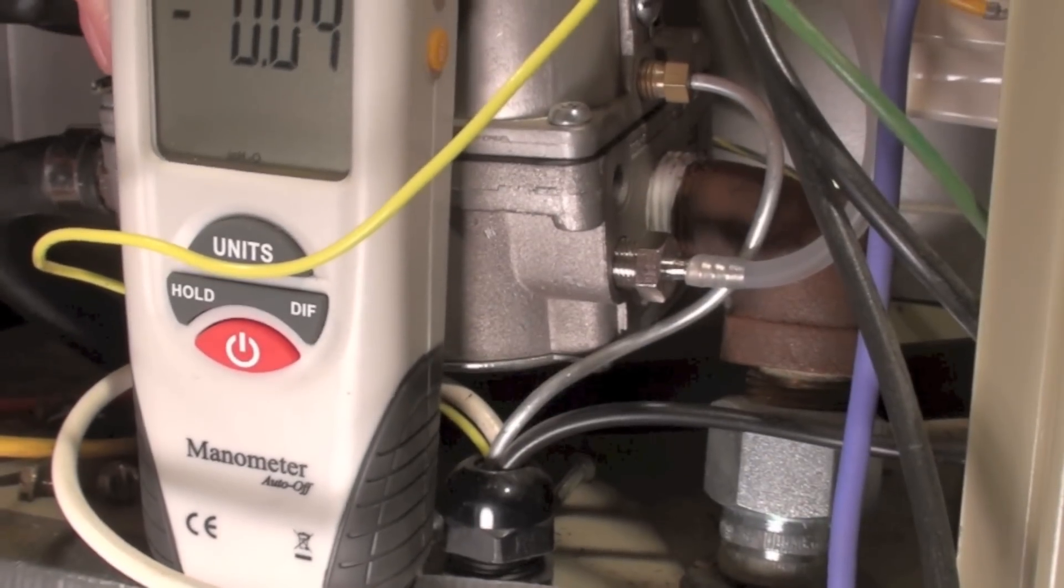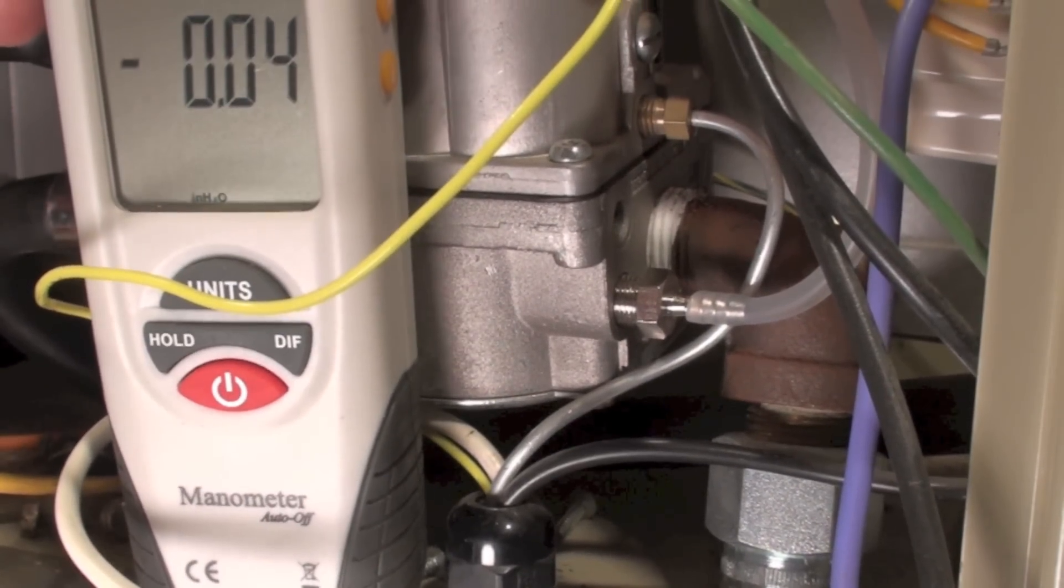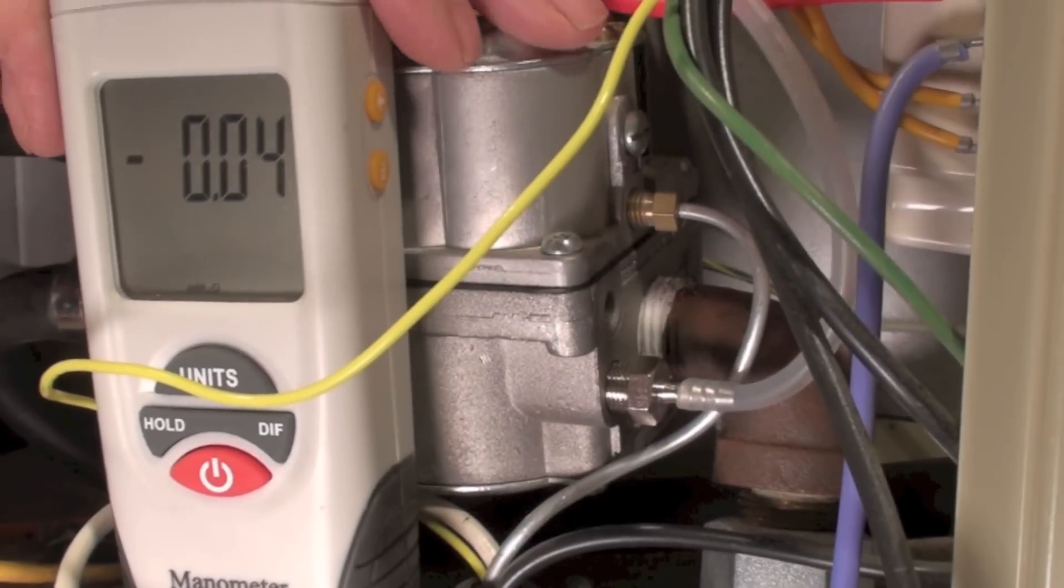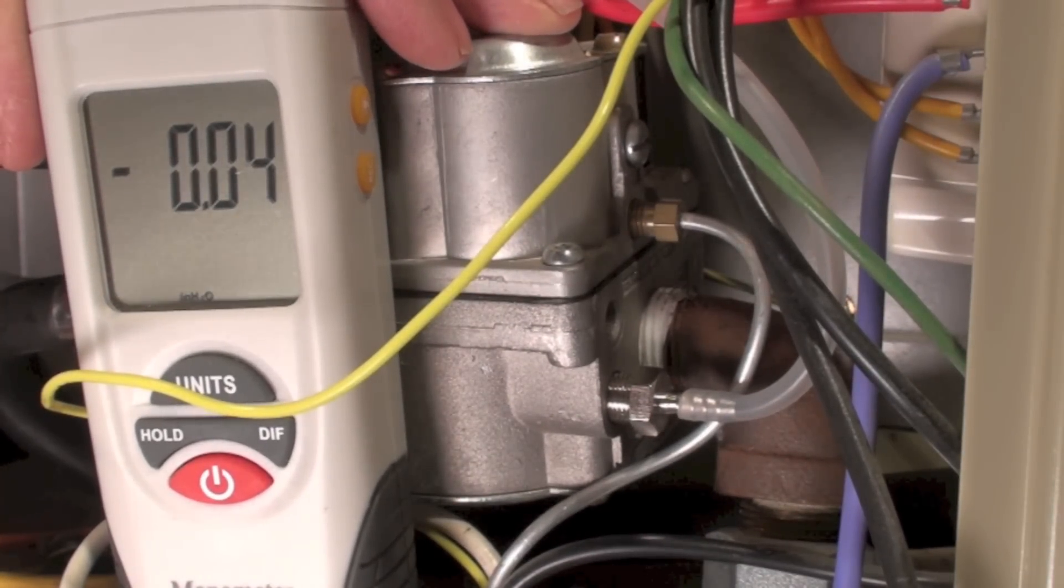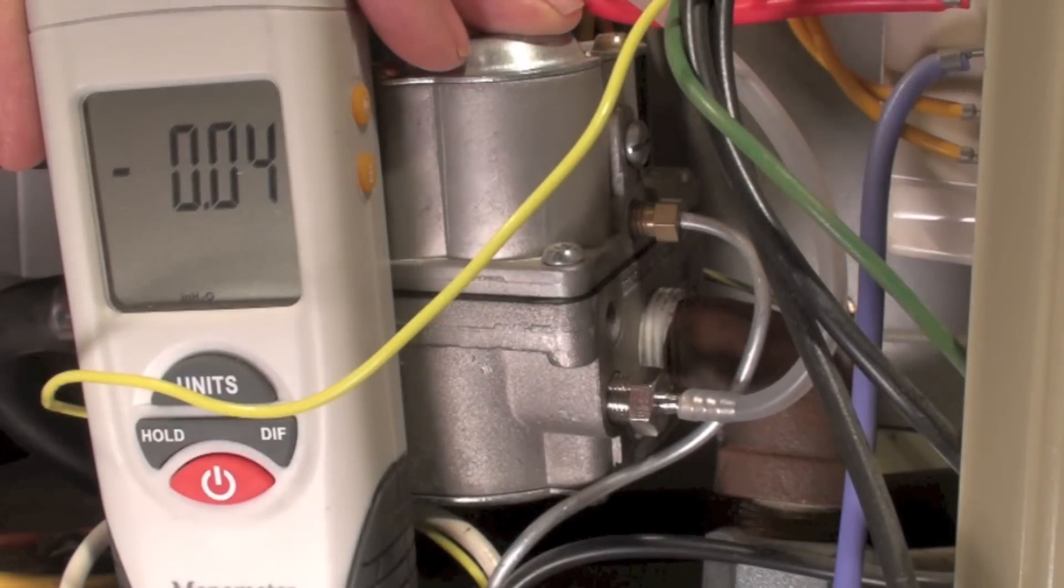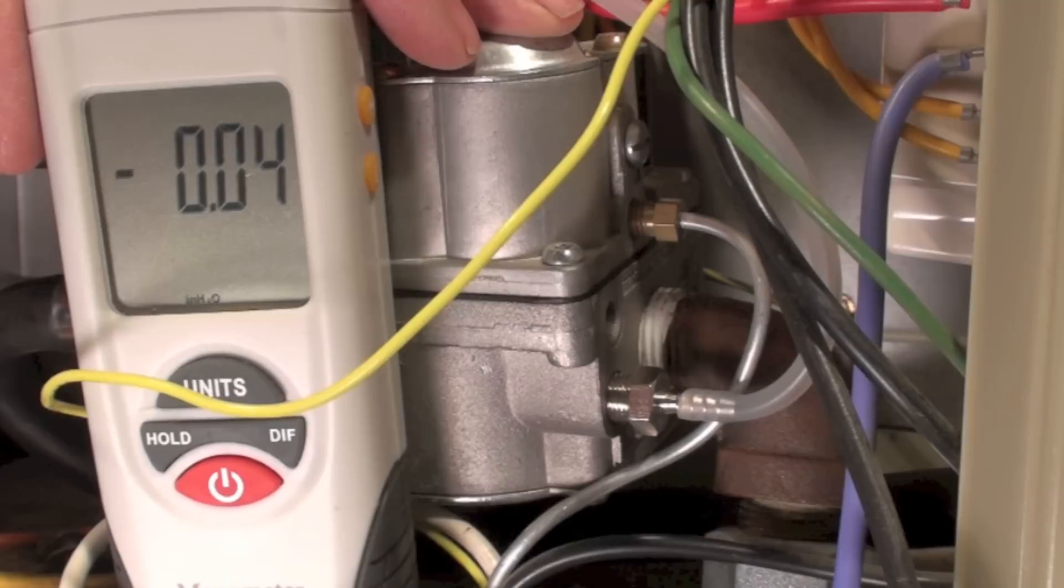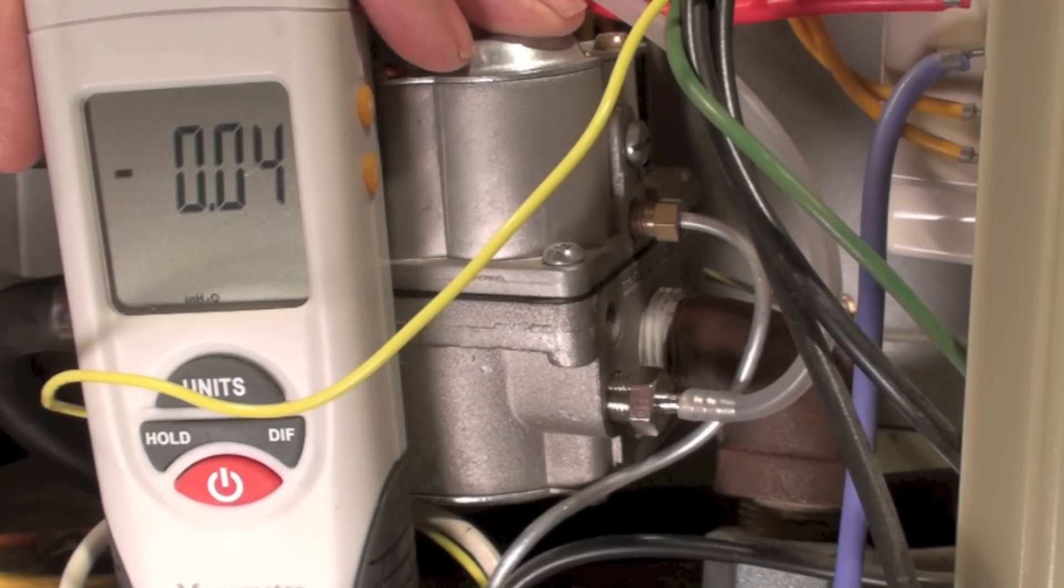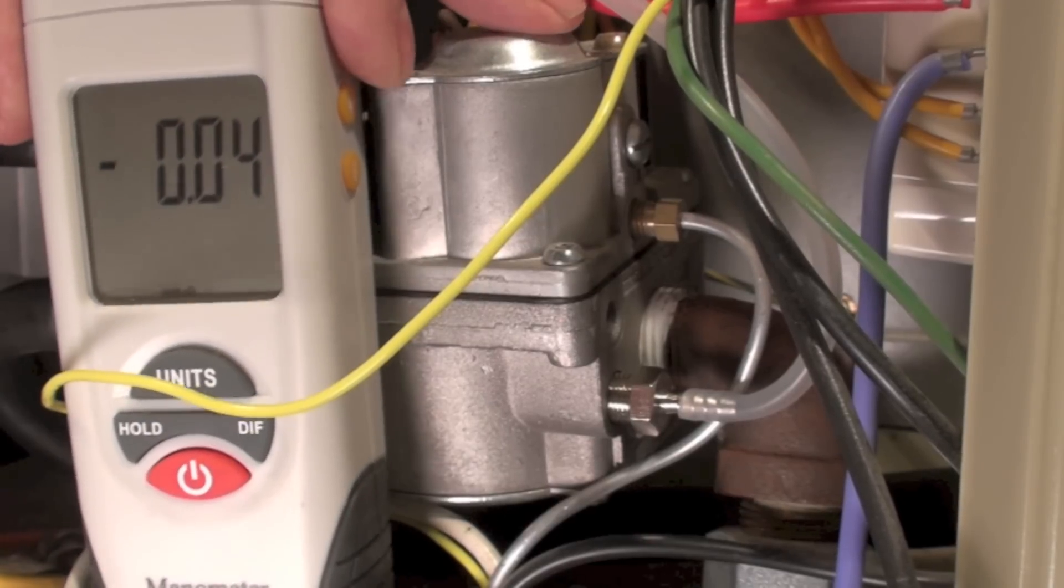When we get manifold pressure on this thing, we have to reference the combustion chamber because that's where the gas is going. So the regulator has to have an ambient pressure that is the same as the combustion chamber. Now I'm going to take that off so that it references outside air while this thing is running and you can see the difference.